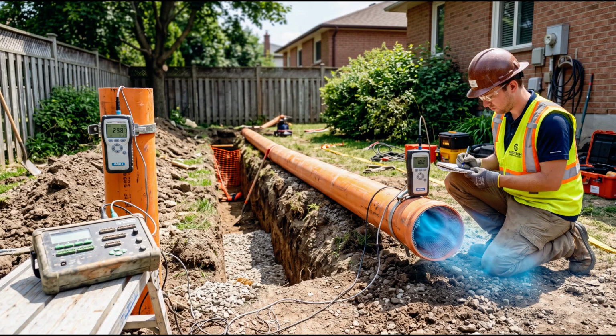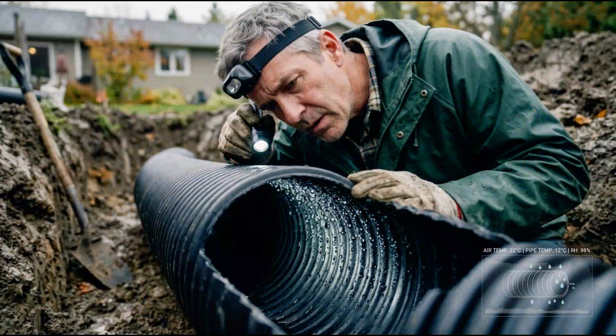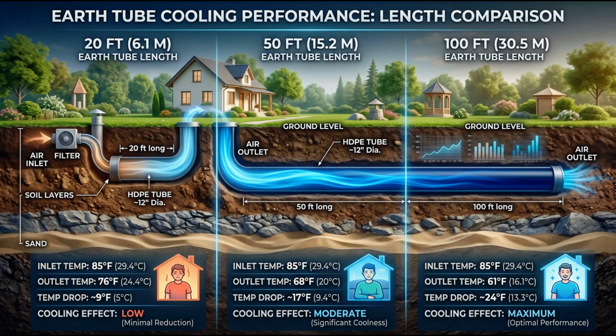We're talking roughly a 50 to 100 times difference in power draw between the two systems. Engineers measure cooling efficiency using COP, coefficient of performance, essentially how much cooling you get per unit of energy spent. A standard AC unit runs a COP around 3 to 4, which is genuinely decent for mechanical refrigeration. An earth tube can mathematically hit COPs in the 20s to 40s range. That's not a modest improvement you'd round up in a sales pitch, it's an entirely different category of efficiency.